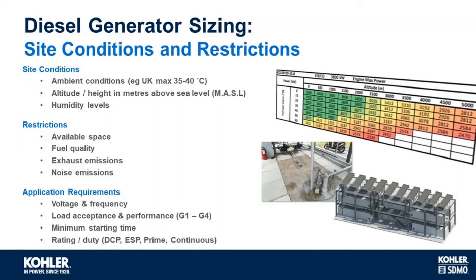So what are the restrictions? Well, available space, fuel quality, as not all regions of the world have the same fuel quality, and that can affect the power the engine can produce, the reliability and the service intervals. Exhaust and noise emissions are important because generators are often installed close to noise sensitive areas such as residential. The application requirements are the voltage and frequency, the load acceptance and performance, the minimum start time, and the rating and duty types that I've just touched on.